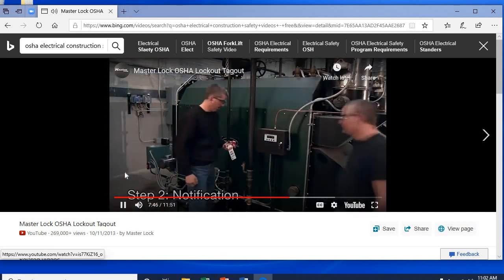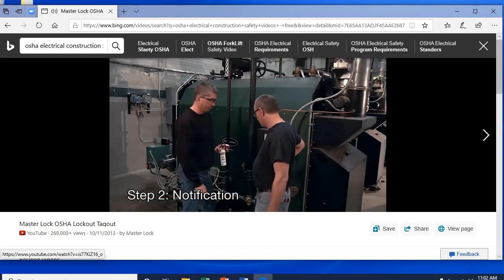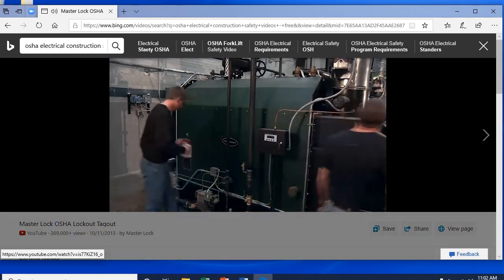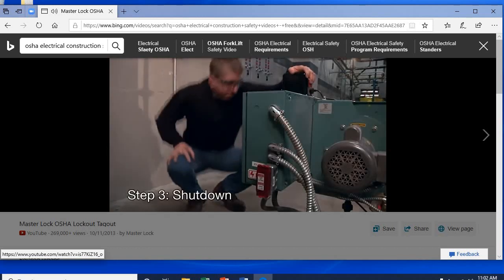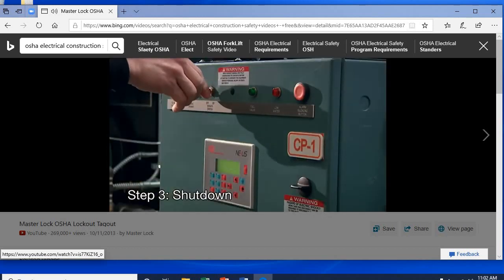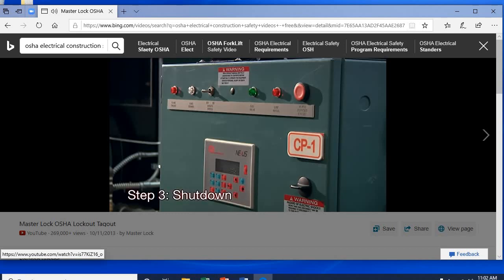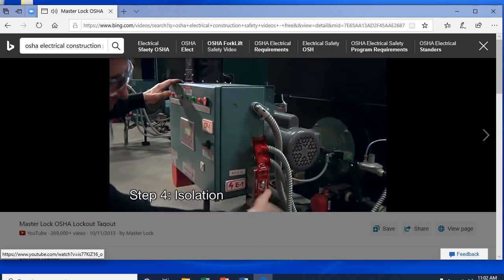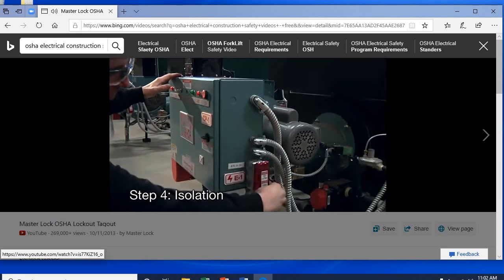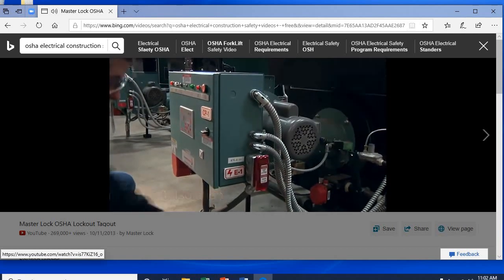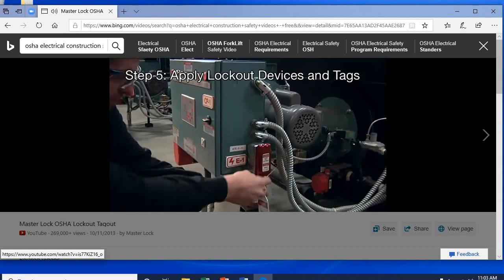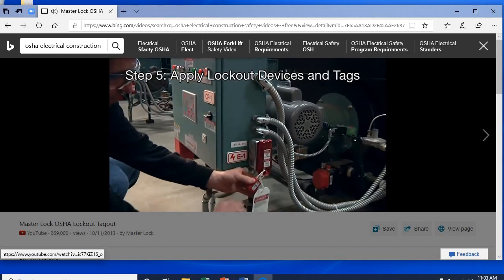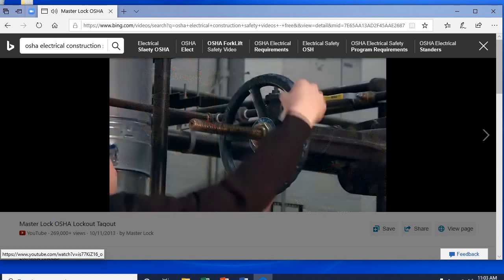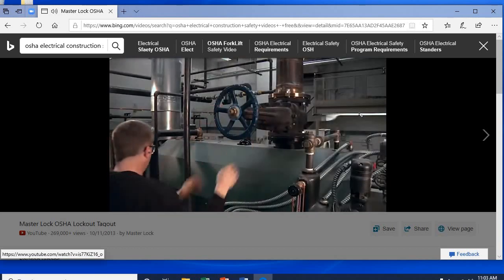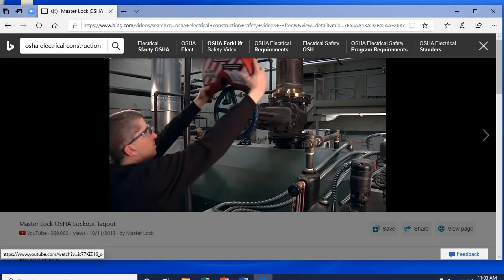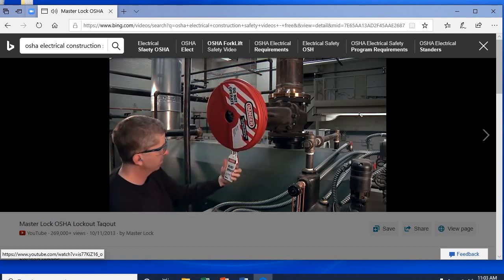Next, notify all affected employees that you're ready to start a lockout procedure. Step 3. Stop the equipment by following its normal shutdown procedure. Step 4. Isolate the equipment by turning off the energy at the main power source. Step 5. Apply a lock and appropriate lockout device to each energy isolating device. Each lockout point that is detailed in the lockout procedure. For example, a gate valve needs a gate valve cover.